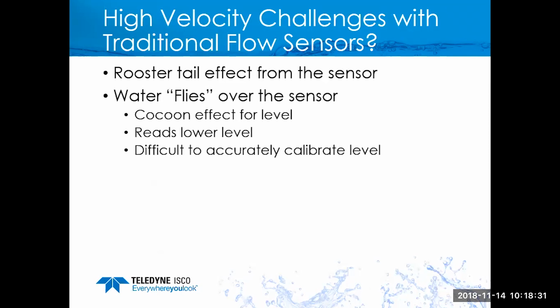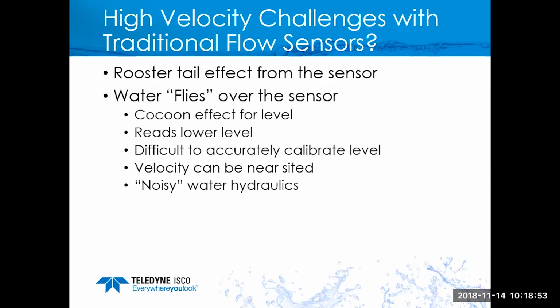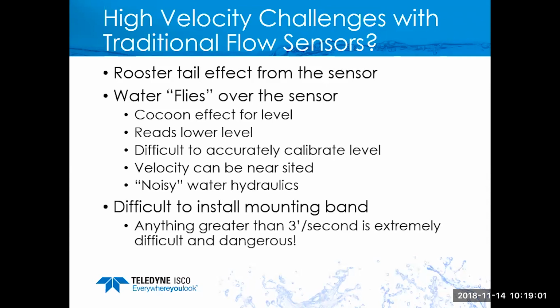It's also very difficult to calibrate when you have high velocity. Those of you that have installed and calibrated know it better than me. You stick a ruler in the high velocity site, good luck getting a good accurate reading. Velocity can also be nearsighted. The particles coming at the sensor are coming so fast that it can get a little bit overwhelmed and be more nearsighted, and that's due to the noise in the water hydraulics. It's also difficult to install a mounting band. For anything greater than 3 feet per second, the people I've talked to have said that is almost impossible to do. So it's impossible, difficult, and very dangerous.